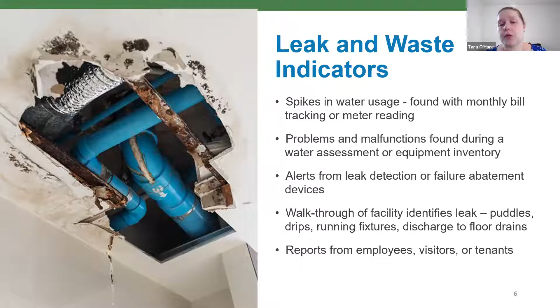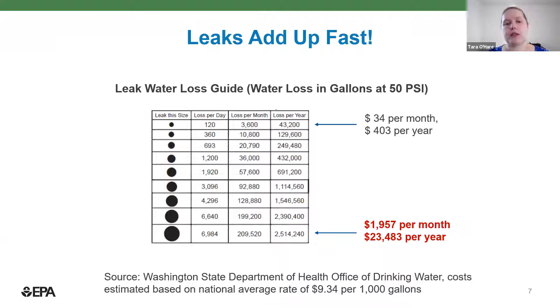Just to give you some perspective, the size of a leak can really add up to significant amounts of money. A small leak is about $400 a year on average in losses, but a leak the size of a pencil eraser can be $23,000 per year on average, which is really significant for such a tiny leak. So the name of the game is to find it as soon as possible and fix it.